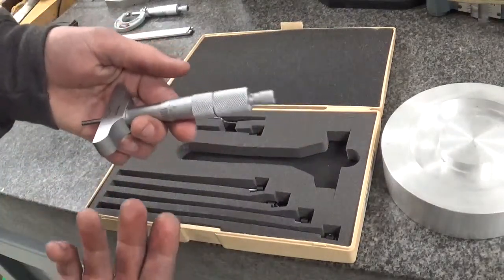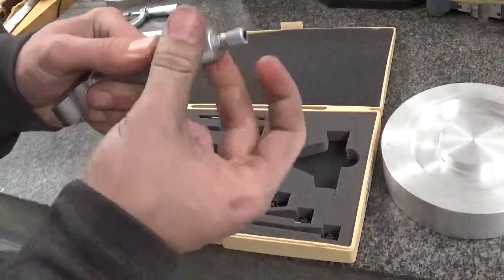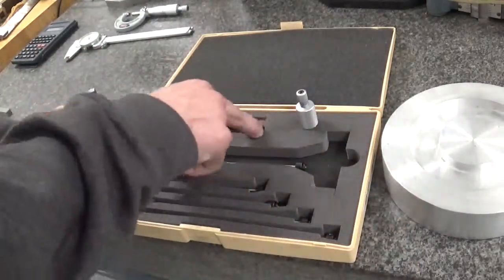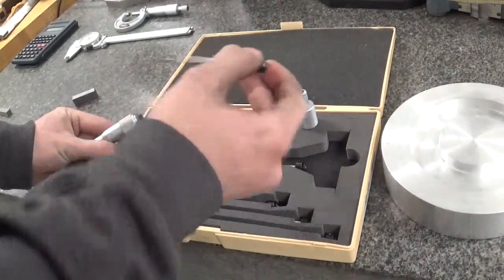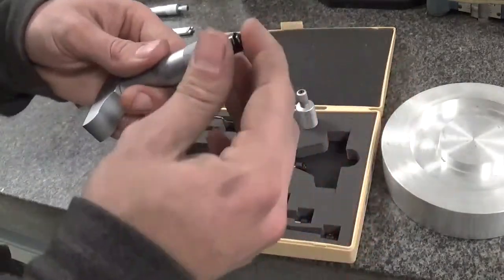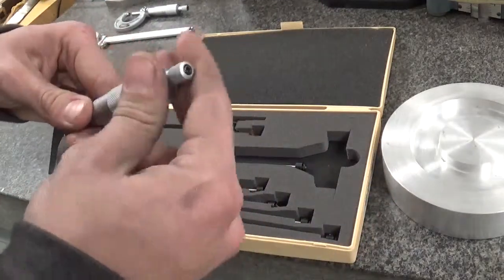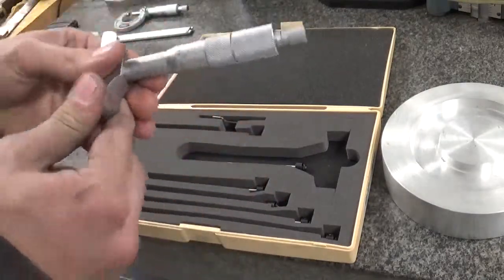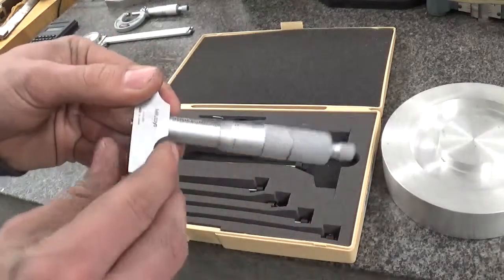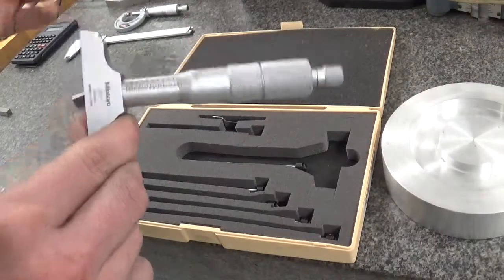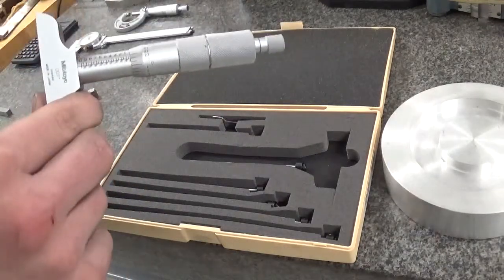To change them, all you have to do is unscrew this, take your rod out, put your desired rod in. I will be taking the 0 to 1 inch, slide it in there, take your cap here and put it back on. There you go—you are not quite done yet though. Before you go here and start taking measurements, you need to calibrate this tool to make sure it's reading accurate numbers.